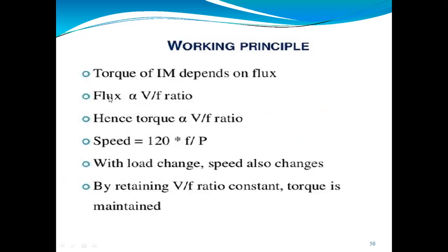We can regulate the flux and maintain the value which will be required by maintaining this ratio. And torque is proportional to the V by F ratio. So here the speed will depend on the frequency. How? Synchronous speed you will get is 120 F upon P.